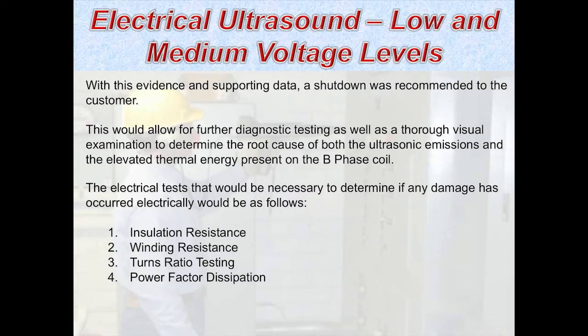Now, we agreed a moment ago that looking at the FFT in the time domain, this is not some type of electrical fault in nature, right? It's something mechanical, and that's undetermined at this point. But can mechanical things that go wrong in a unit like this actually cause an electrical failure? They sure can. And that's the concern here, especially with a 5-year-old unit. So we're going to be looking at things like this. And those of you involved in the electrical field, you know what these are.